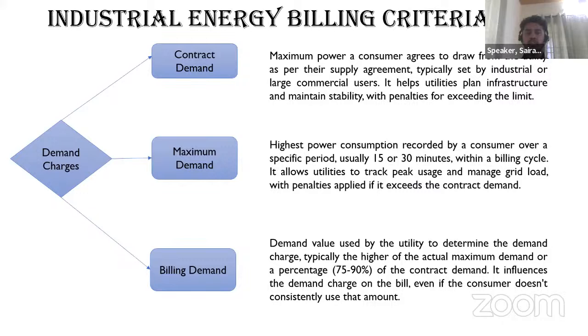If you set a contract demand of 1000 kVA, then the billing demand will be in the range of 750 kVA to 900 kVA. If your maximum demand exceeds 900 kVA, then you have to pay for the amount that goes beyond the 900. If you are consuming only 600 kVA, then you have to pay the limit that is set by the billing demand, either 80% of the contract demand or 90% of the contract demand. You have to pay the grid as you promised in the agreement.